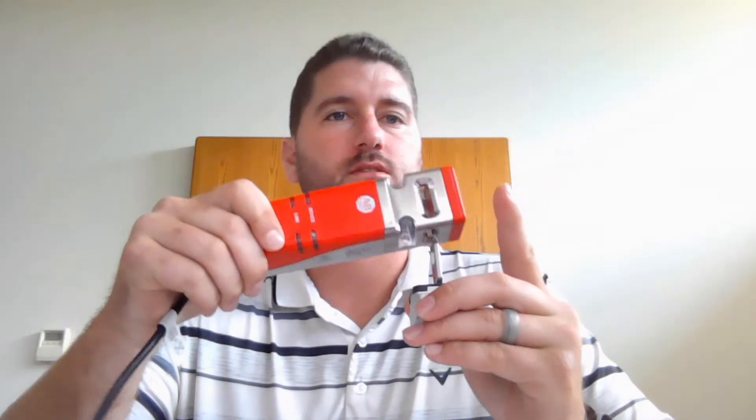There's a locking pin that will hold it shut, and it can be used with Guard Link. If you're using Guard Link and want to use this switch, all you need to do is get a passive tap. Or you can use a safety relay with an Ethernet module and connect this device into your safety circuit via Ethernet.